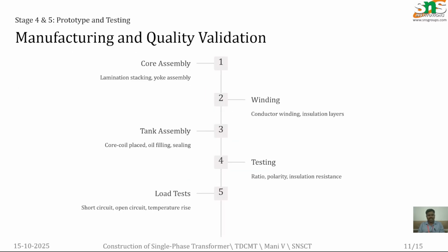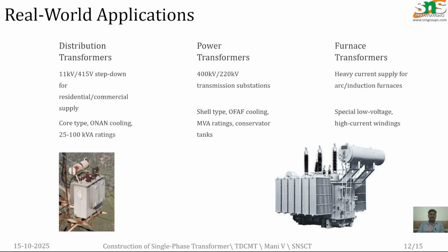And this is the manufacturing and quality validation. Here the core is assembled, and the primary winding and secondary winding will be tested and wound on the transformer core. Again the tank will be assembled with the oil filling and perfect sealing, and with the help of tests like the ratio test, polarity test, insulation test, open circuit test, and short circuit test, everything will be tested. And finally we are dispatching the system. So this testing and load test, everything comes under the testing part.